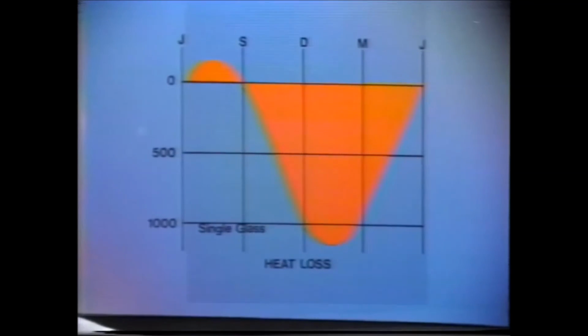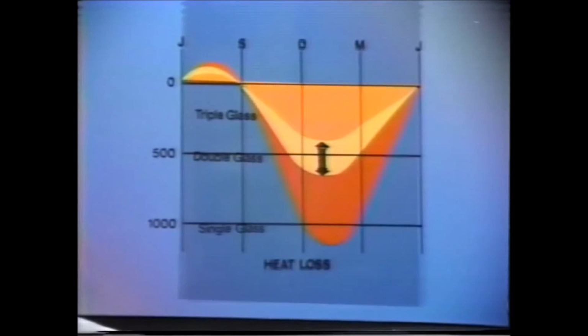The average 24-hour heat loss through the window is plotted for each month using room and ambient temperatures. Note that the heat loss of double glass exceeds the heat loss of triple glass much more than the solar gain of double glass exceeds the solar gain of triple glass.